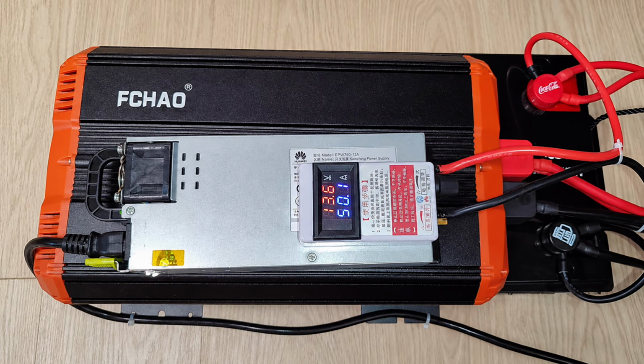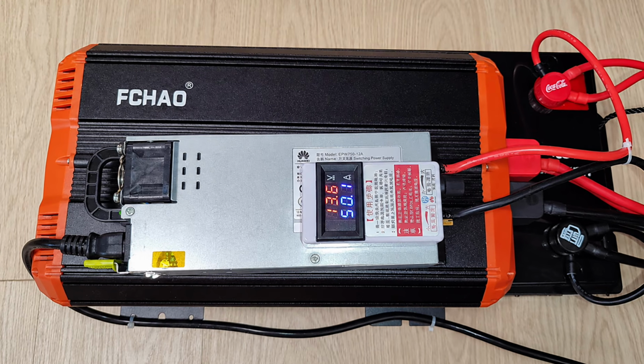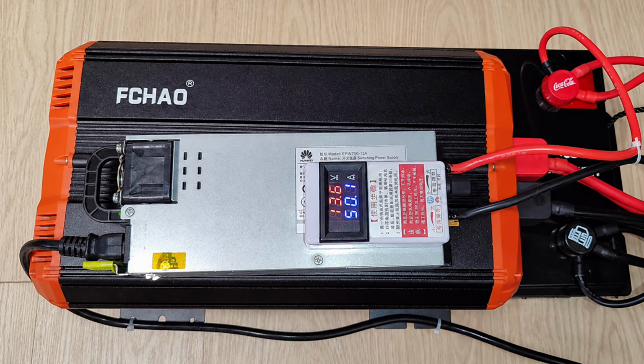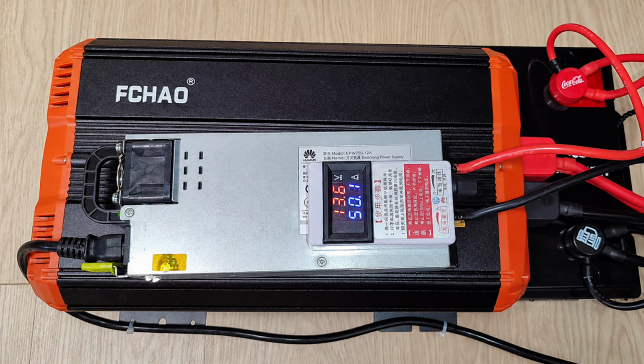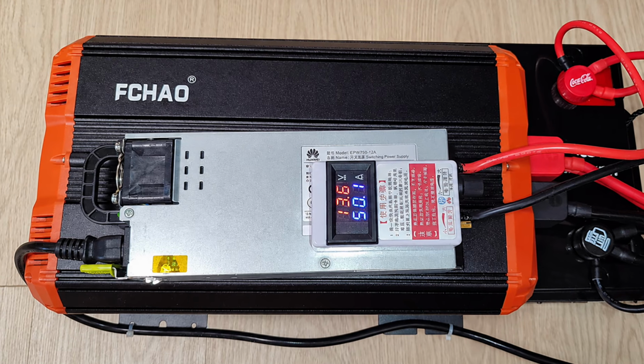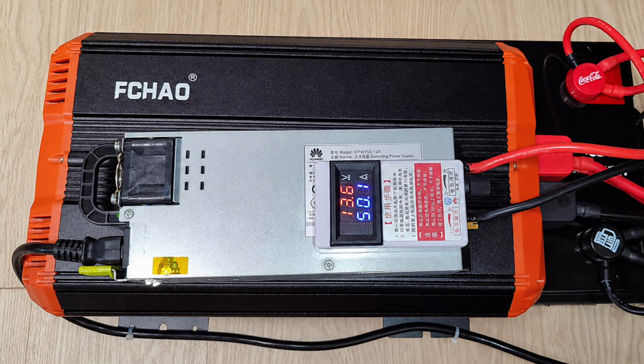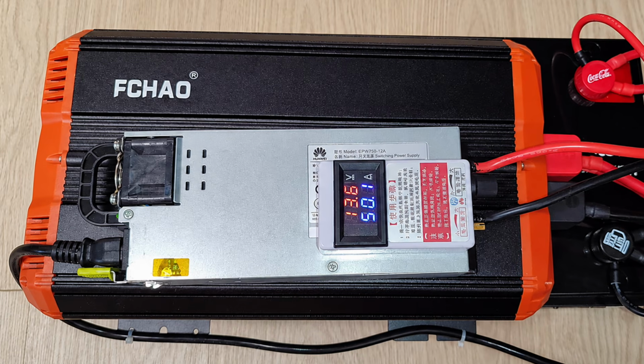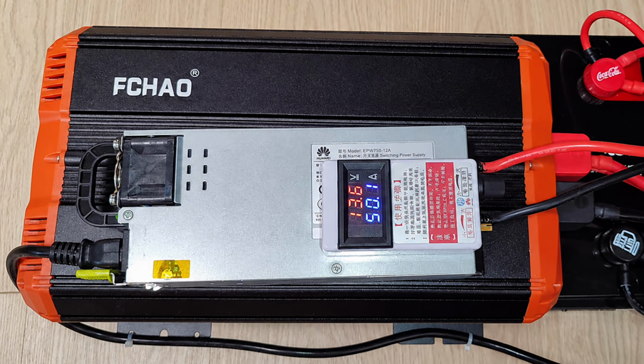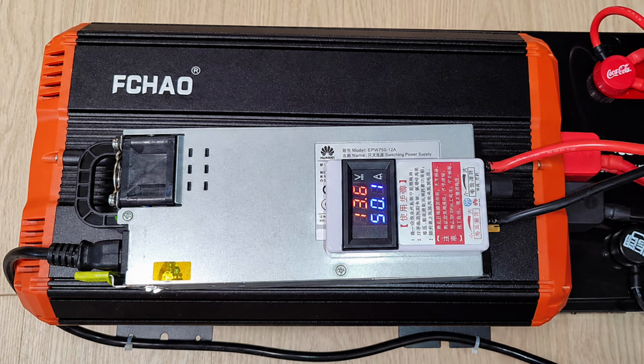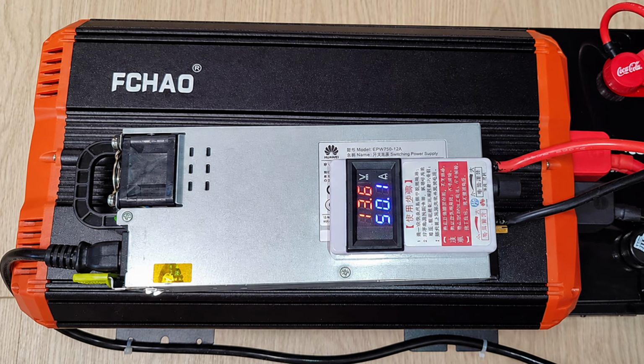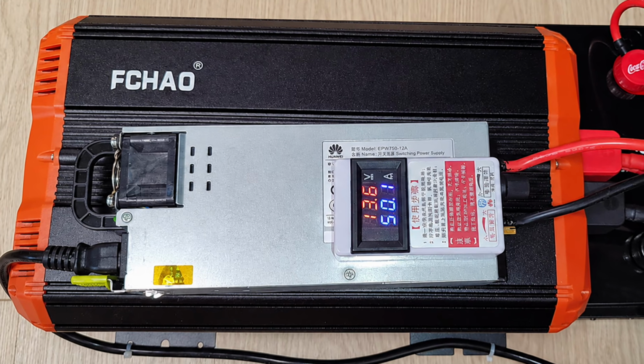In this case, I limited the charging current to 50 amps. The charger is connected directly to the battery and can operate simultaneously with the inverter. If the inverter consumption on the 12-volt side is less than these 50 amps, the remaining current goes to charging the battery. If the load is higher, part of the energy comes from the charger and the missing part is taken from the battery.